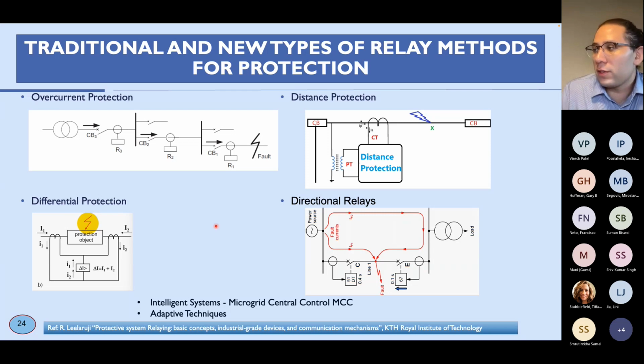Then we have the distance protection. Distance protection is used most commonly at transmission level. Nowadays, differential protection, distance protection, and directional relays are mostly used at transmission level or distribution substation medium voltage level. The common one, overcurrent protection, is used in low voltage. But as I showed before, with the penetration of inverter-based resources, we need to address different types of studies because we now have different types of operations.